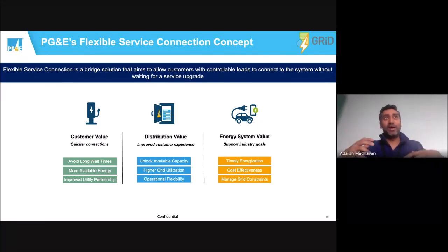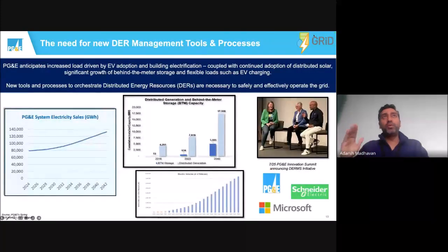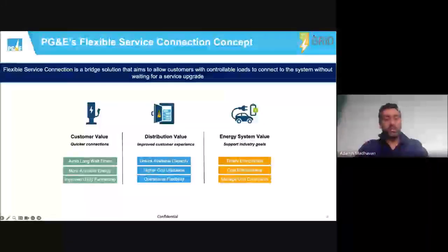So when I'm talking about flexible loads, it's easy to think about inverters, but we're also talking to corporate campuses willing to put in behind-the-meter generation, and to us that's a flexible load too. You dispatch your generation, and the amount of power you consume at the point of common coupling goes down, that counts as flexible load for flexible service connection purposes. If you're willing to participate in the dynamic limits being sent out, you can connect right now. You don't have to wait for the service to be built out.